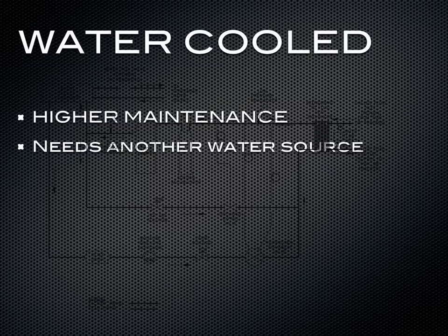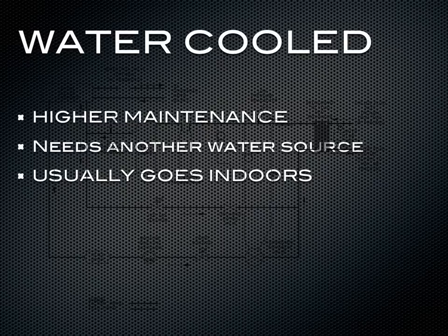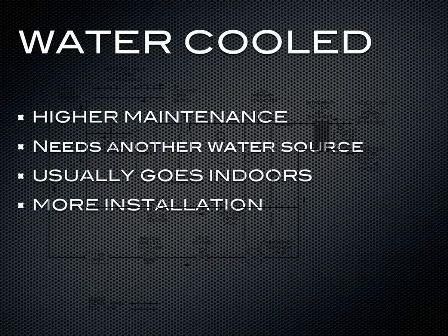Water-cooled chillers typically go indoors, because you don't have to worry about the heat being rejected through fans, so you can put these into more confined spaces like mechanical rooms. If you put it into a confined space, you want to make sure there's enough room around the chiller for maintenance — we recommend around 3 feet. There is more installation on a water-cooled chiller because there's the piping for the condenser side if you're piping it to the building water or a cooling tower. Water-cooled chillers are smaller in size compared to an air-cooled because you don't have the fans in the build.